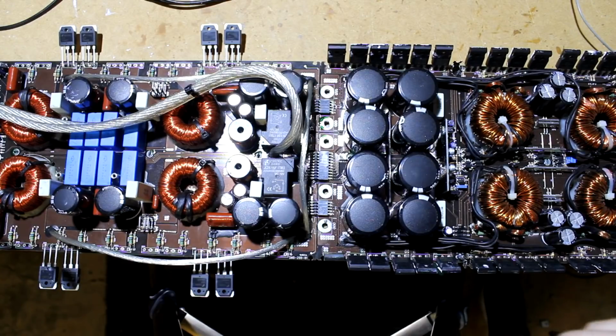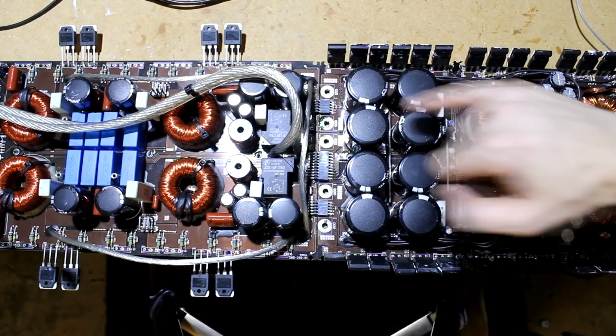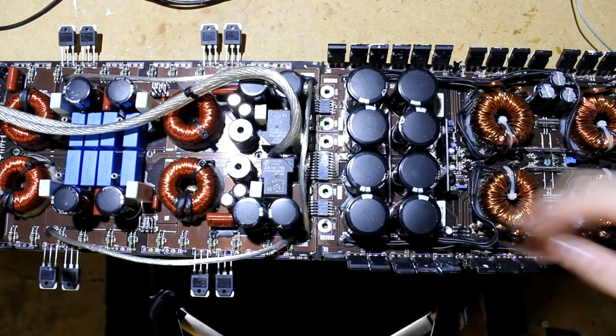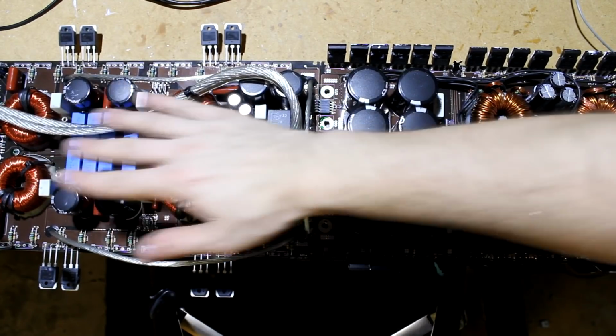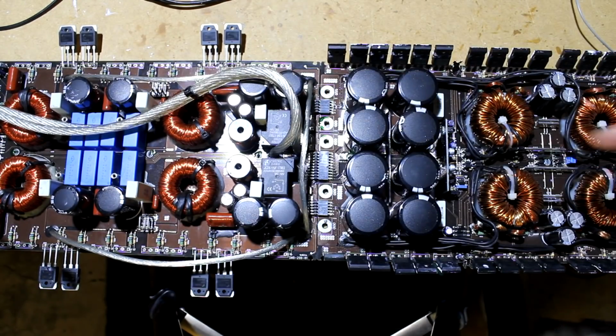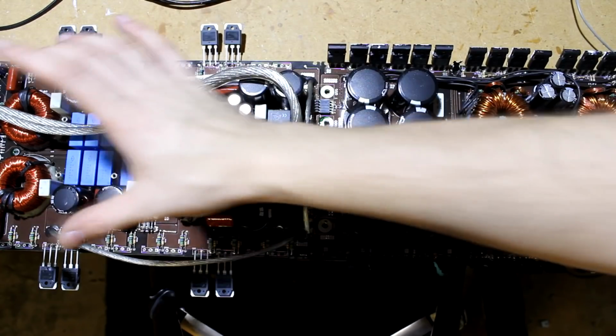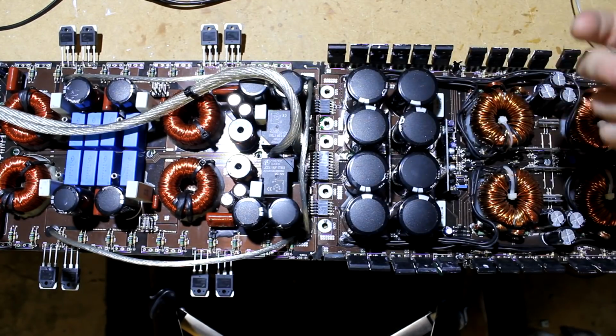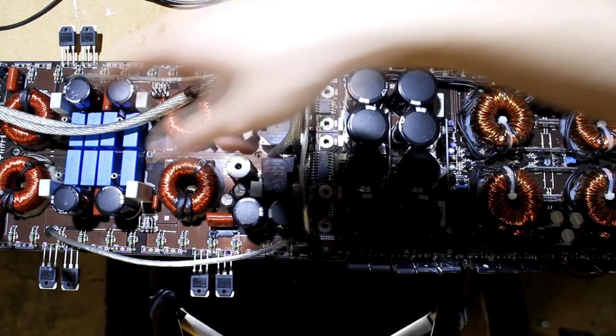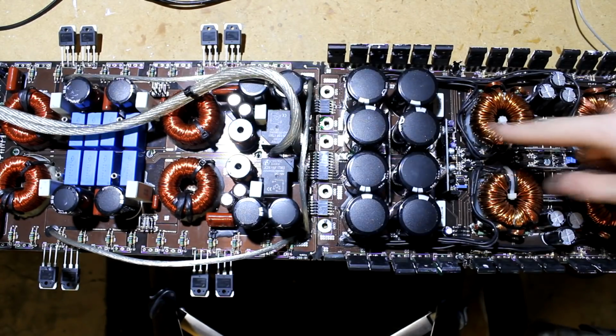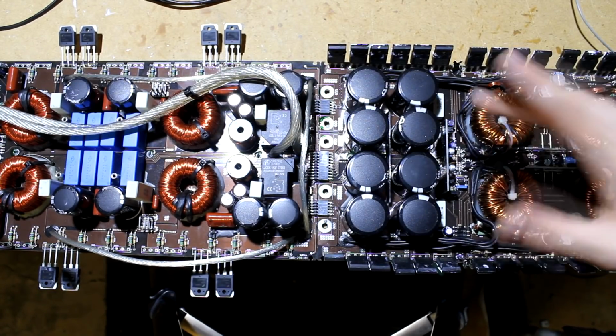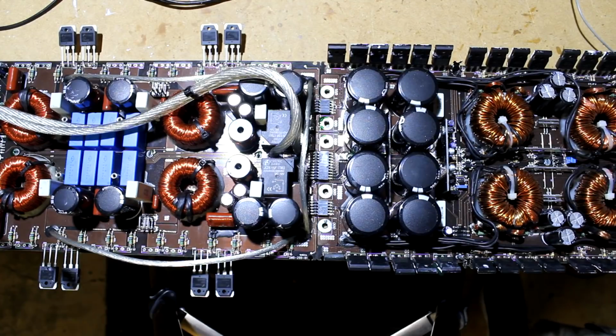Okay, so in order to find this protection circuit fault, we know it's coming from the output section. We know the output section protect trigger is causing this problem, because when we remove the output driver card, the protection issue goes away. So it's something to do with the protection trigger from there, which sends a signal to the driver board for the power supply, telling it to turn off, shutting the amplifier down.